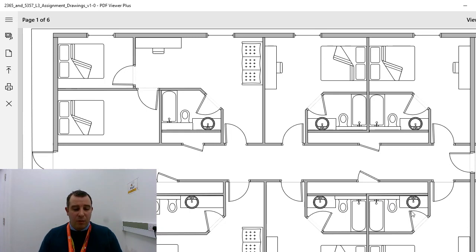What you need to consider when you do that is what circuits are going to come out there. If you've got a particular room, say this is a room, all the circuits from that fuse board have got to be within that room. You can't interlace them between rooms, yeah? You can't go between rooms. So you can't say one fuse board here, and I'm going to ring a circuit that goes round 2 rooms. They've got to be independent circuits, yeah?